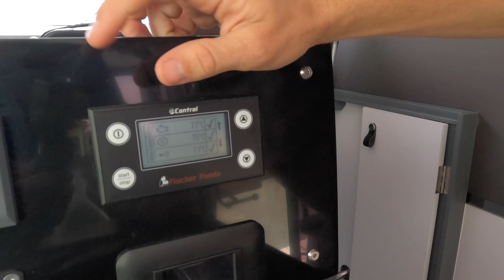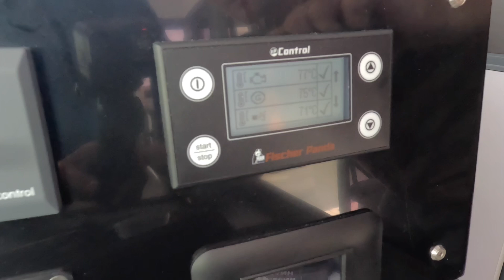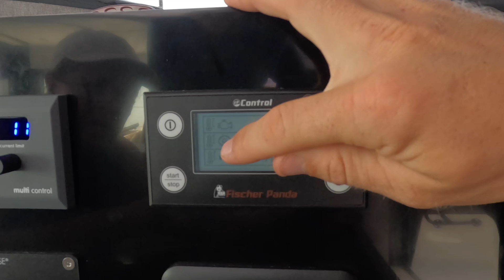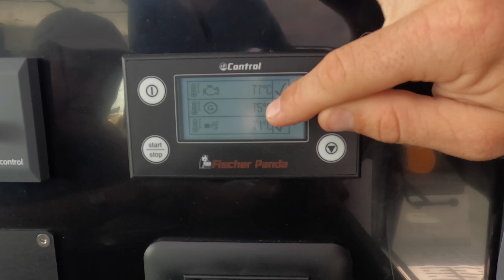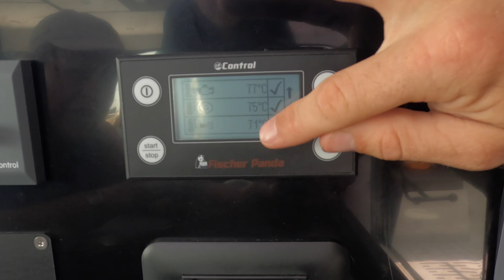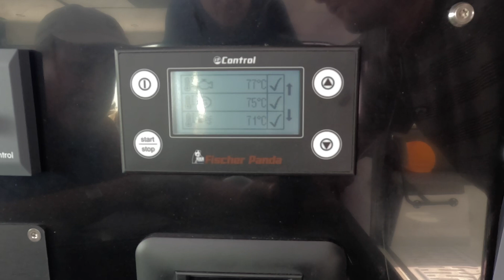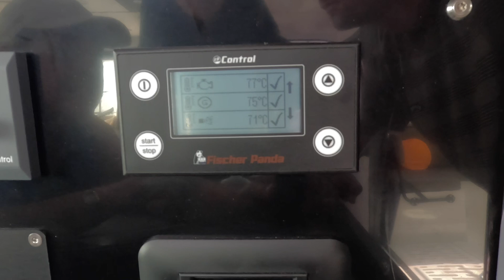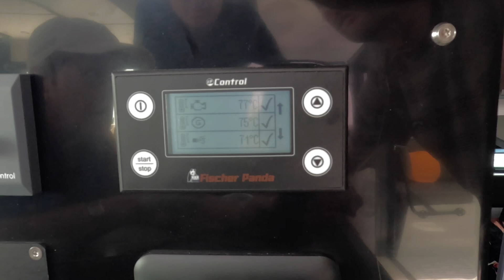When is it too hot? This sensor was really in the middle of the genset, in the oil actually - too hot would be more than 90-95, currently it's 77. The other one, I don't remember exactly where the sensor is, but too hot is more than 95-100. And the exhaust - same thing, the exhaust temperature should not go over 85, 90. That's Celsius, yeah, that's really hot, it's always like this.